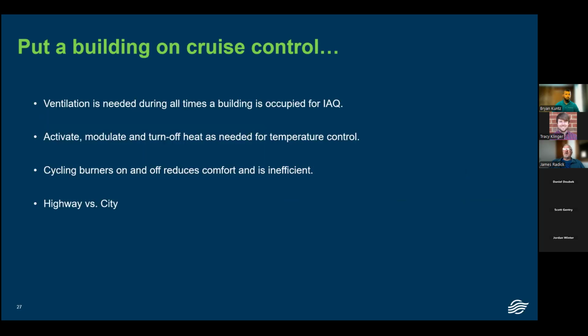Okay, so with that 30 degrees, and again, I'm very passionate about this because I've seen it work for the last 40 years. It's a great concept. Positively pressurize a space, use a low discharge temperature. What happens to that space, that discharge temperature? If your space set point was 65 and the actual was more than 1.5 to 2 degrees below it, our system would recognize that and the dampers would be off doing their thing to maintain the positive pressure.